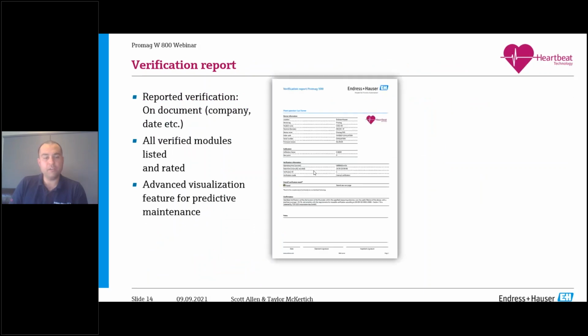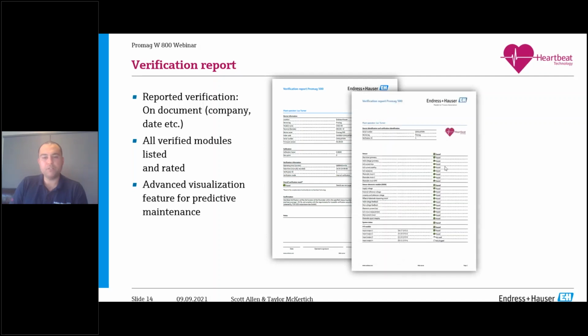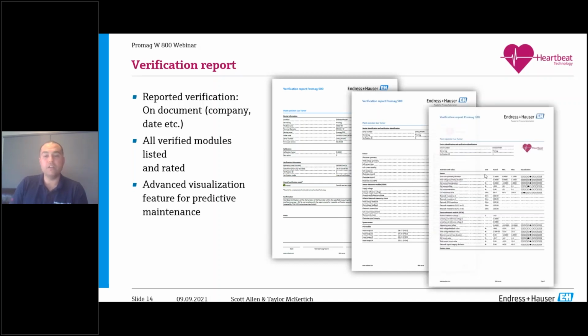You get a full documented report at the conclusion of the verification process, including meter details and all the test results of what was checked, with a pass or fail. There's color coding, basically a tick or cross, showing the threshold diagnostic values and making sure they pass. Conversely, if you get a failed verification, these results can assist with fault finding and knowing what's wrong with the meter.